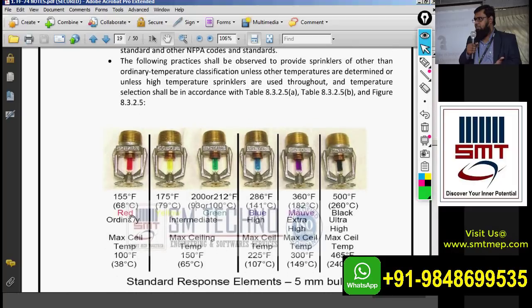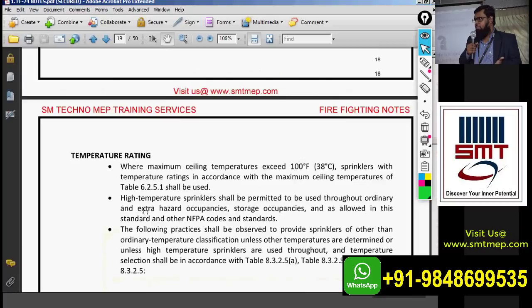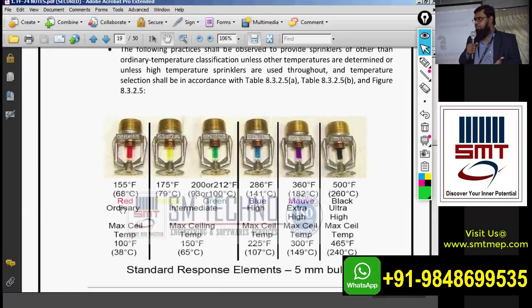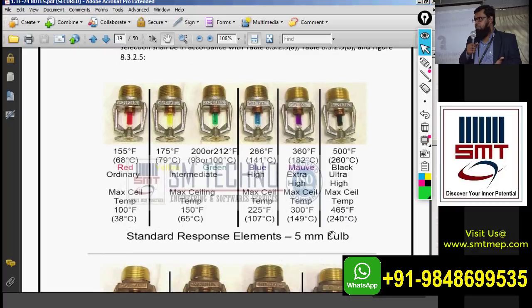The temperature rating table also shows colors. The red color is rated up to 68-70 degrees centigrade; orange is similar. Yellow is around 79 degrees centigrade. For very high temperatures such as furnaces or boilers, the black color is rated at 260 degrees centigrade for industrial applications.